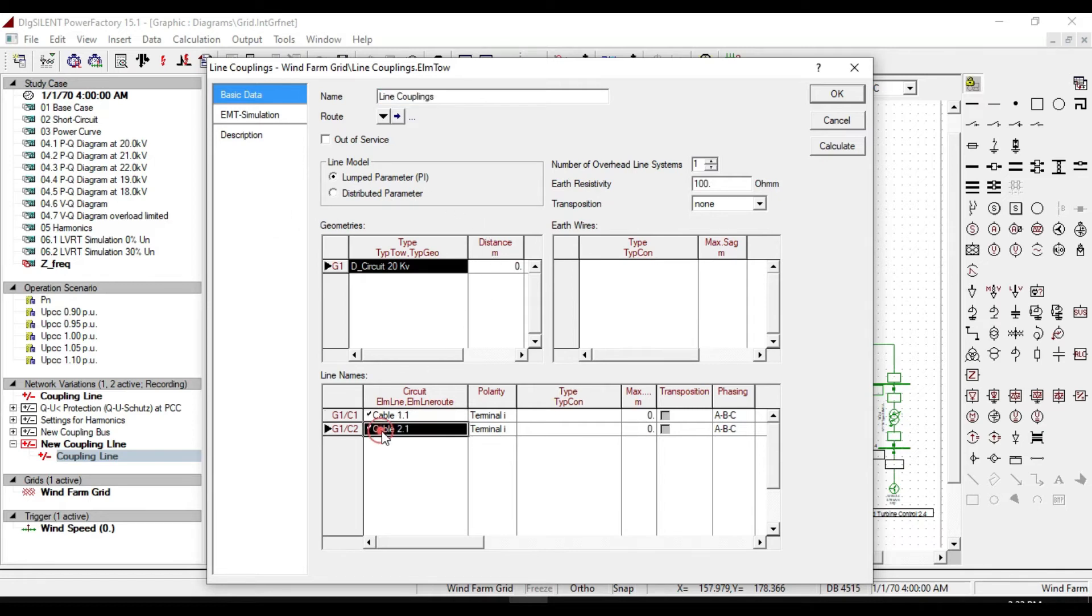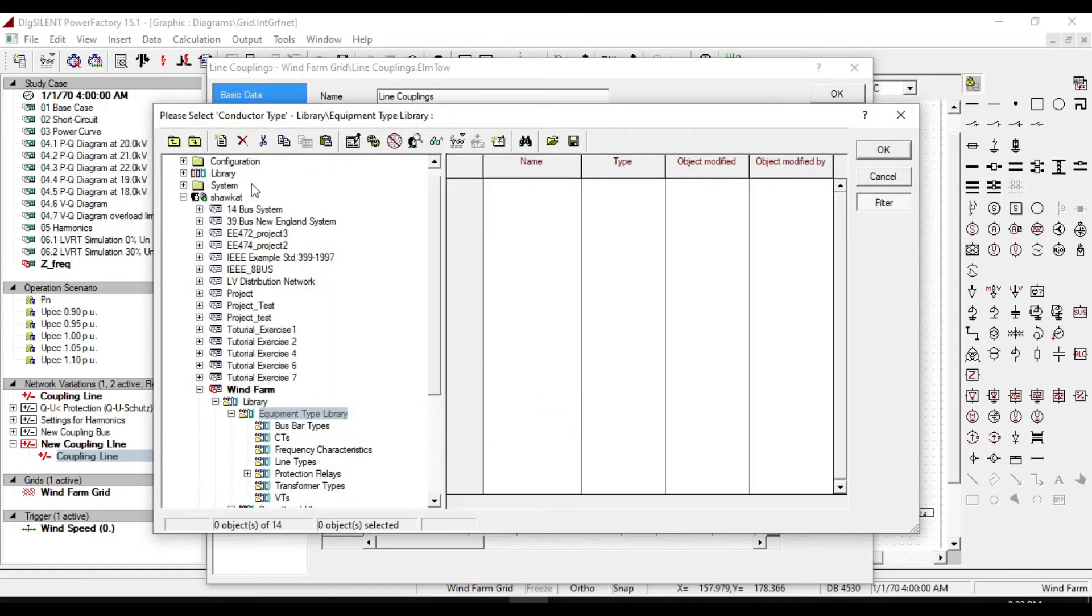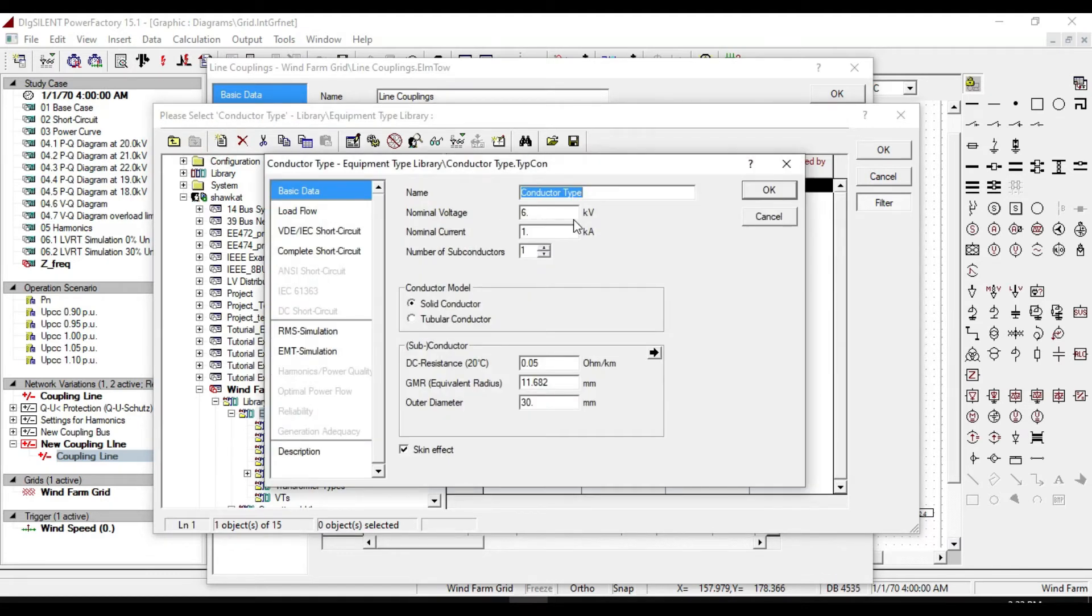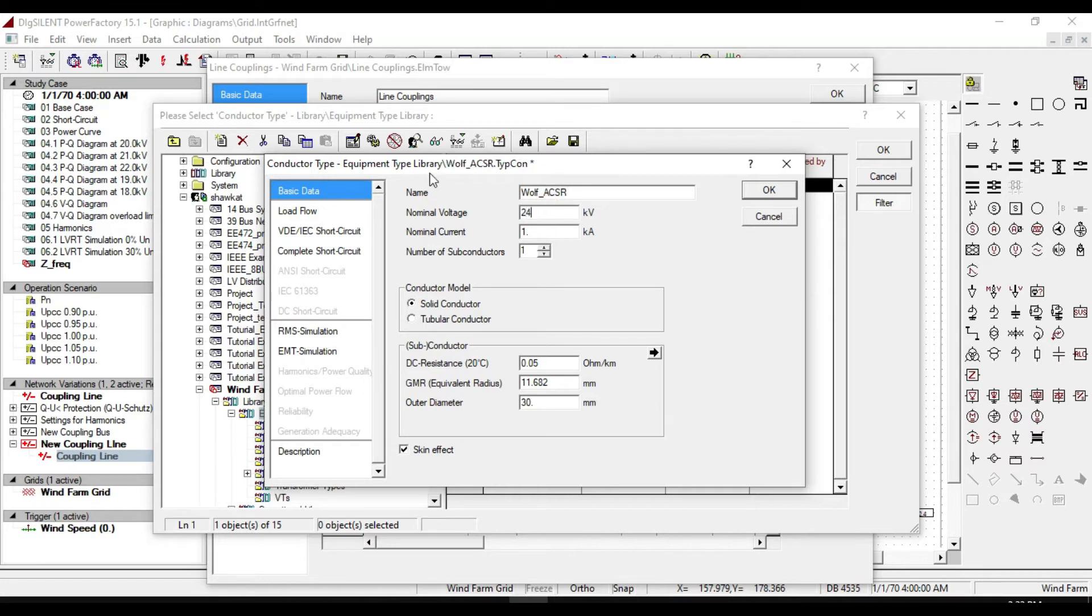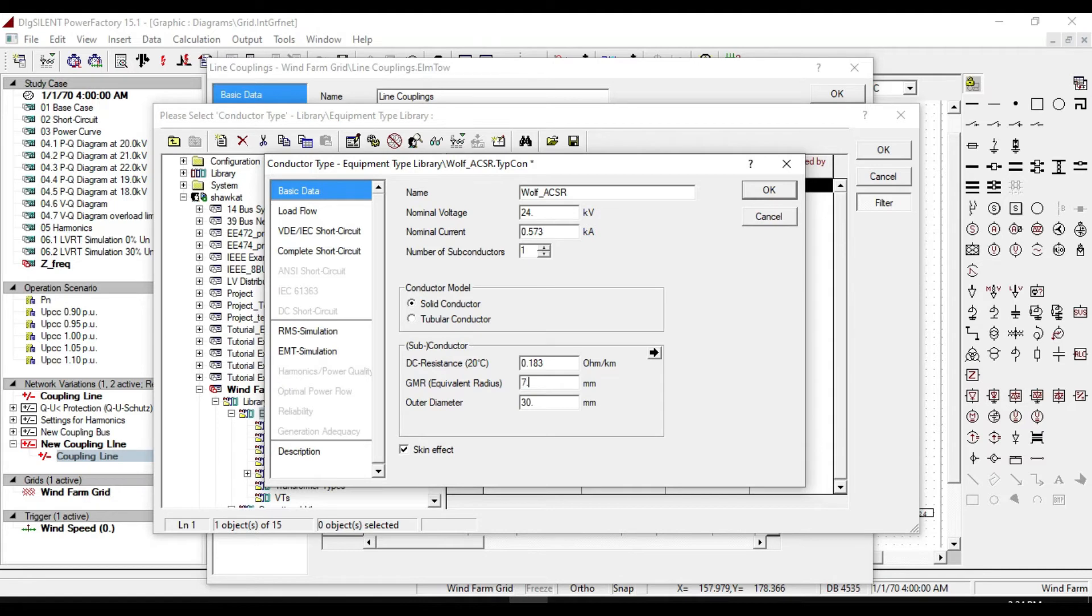Double click it and select line. As you see, cable 21 is selected as default here. Define type for our conductors. Double click here to define a new conductor type. Name it as Wolf underline ACSR. Enter 24 kilovolt as nominal voltage and 0.573 kiloampere as nominal current. For DC resistance at 20 centigrade, enter 0.183 ohm per kilometer.